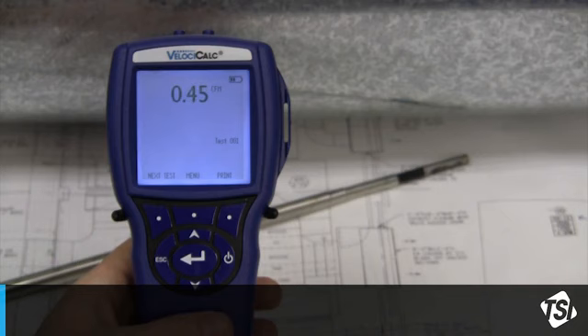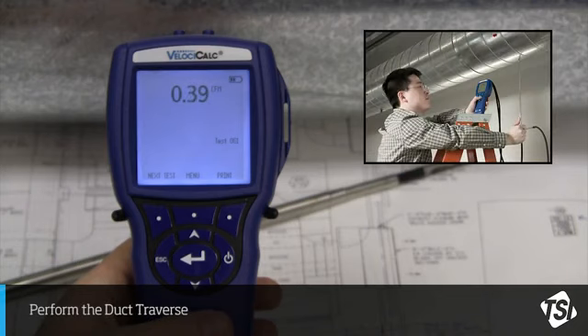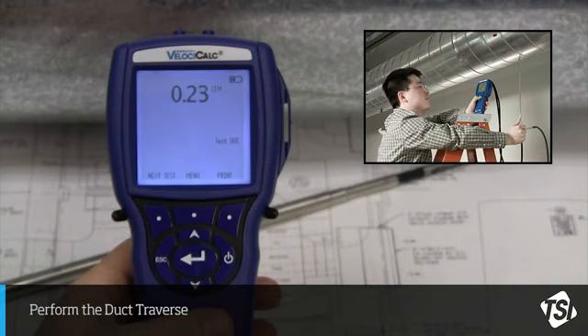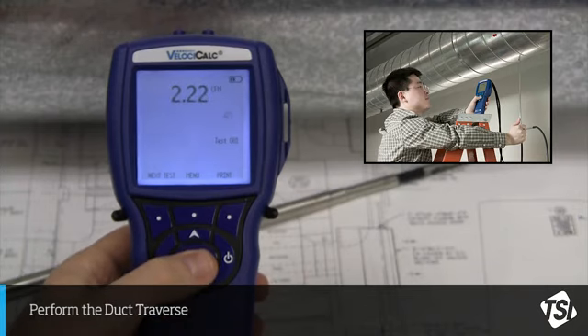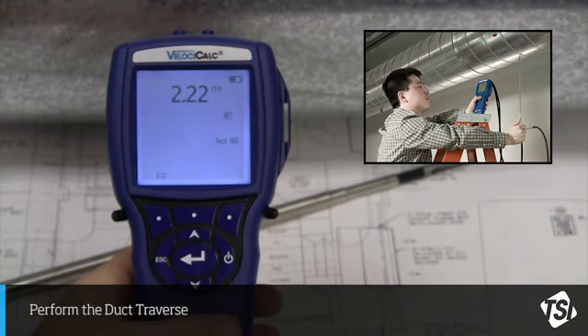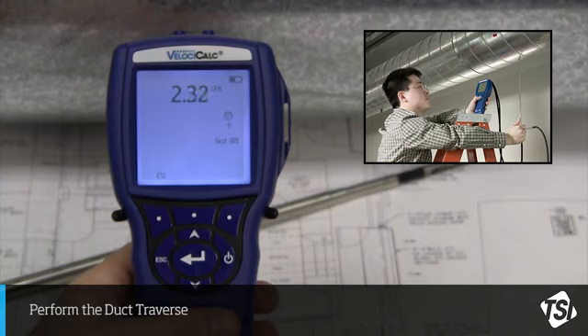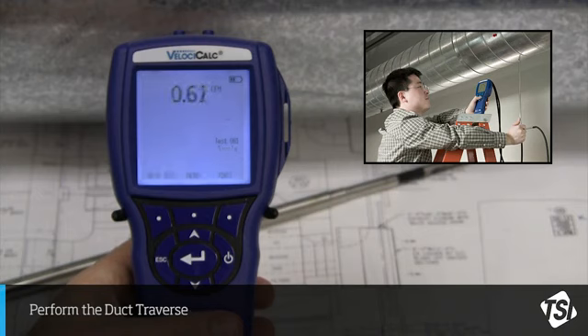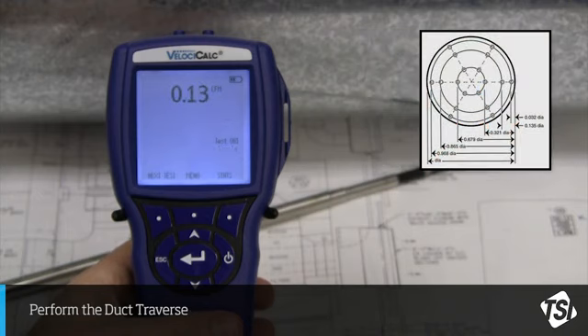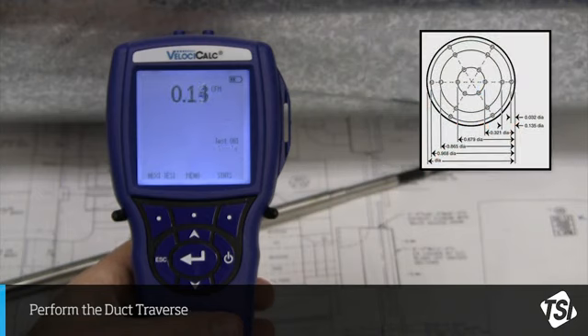Press Enter when the probe is in the proper position within the duct. The unit will display a cylinder with an arrow pointing to it and it will count down from your selected sample time. In this case, it will count down from 10 according to the sample time I selected earlier. I would do this same step, pressing the Enter button and waiting for the 10 second countdown, at each of the points in my duct traverse.